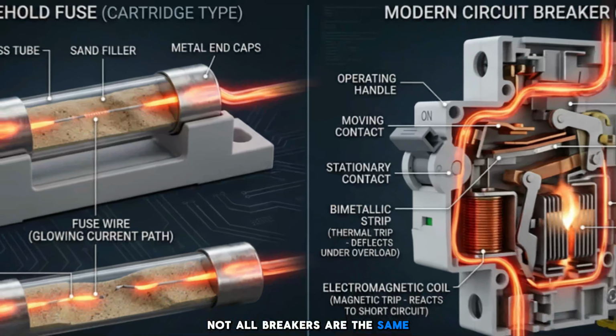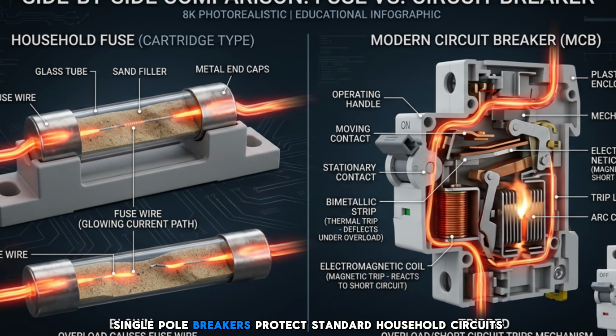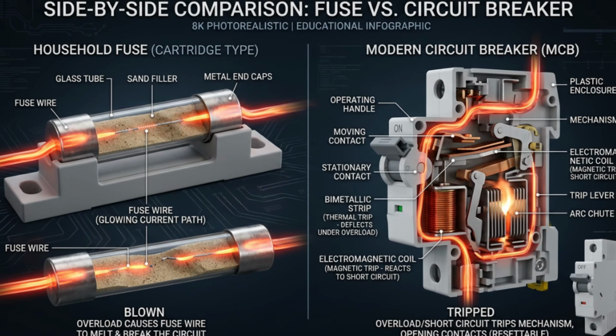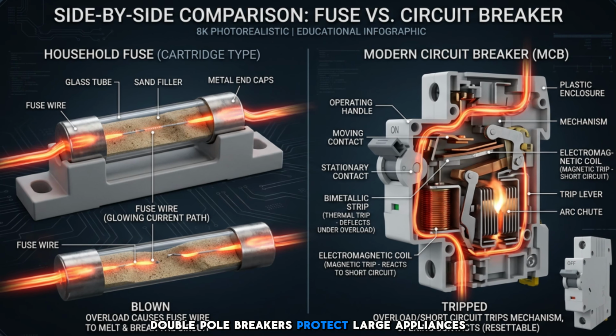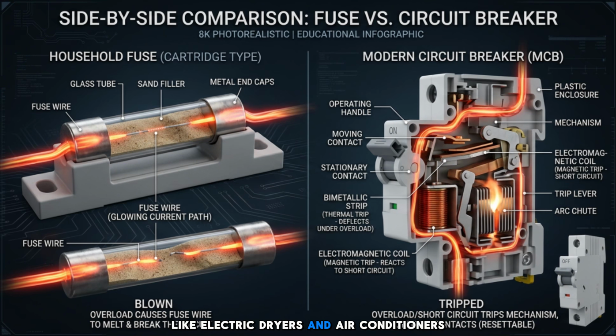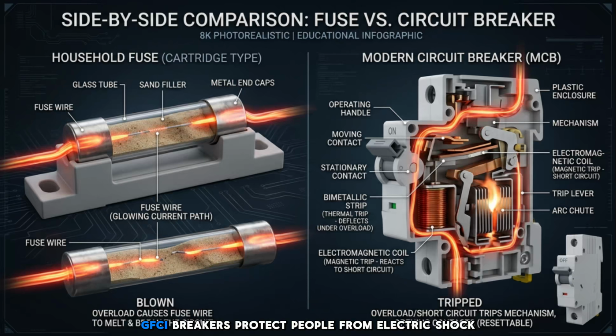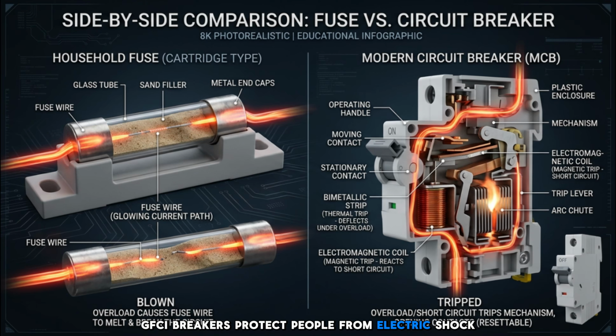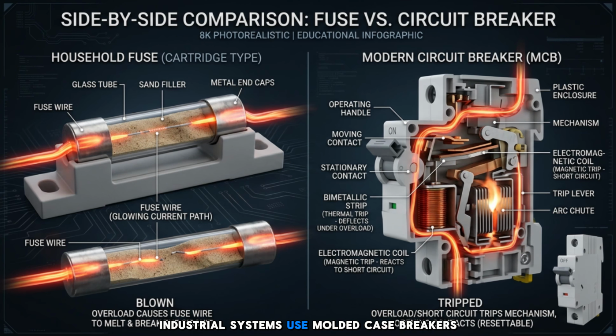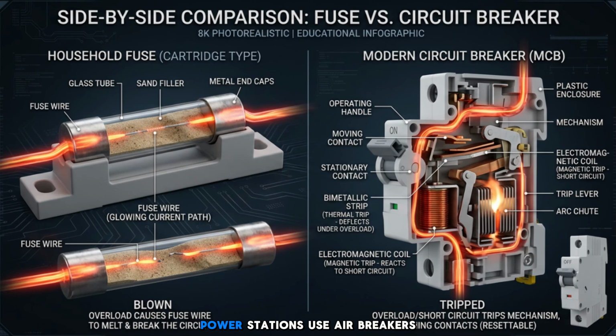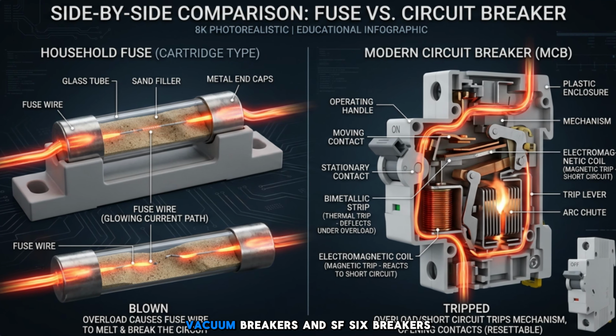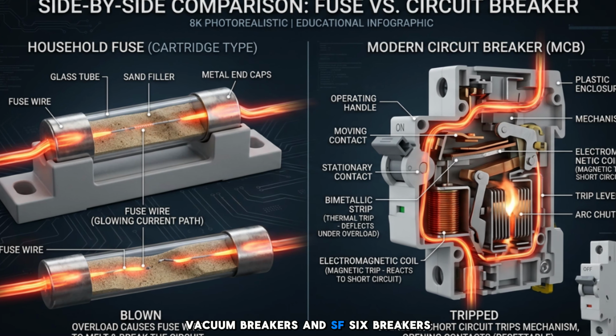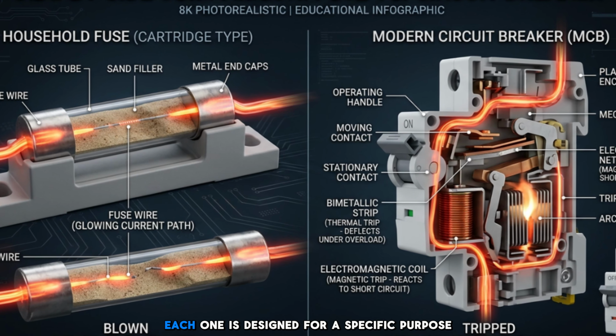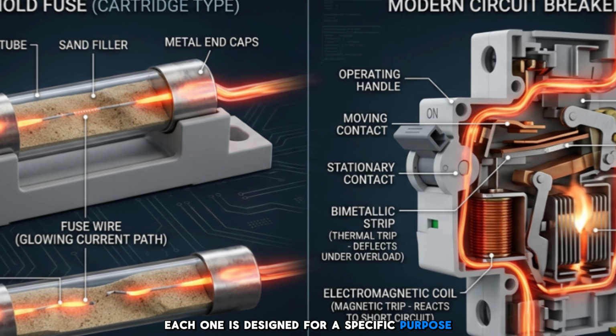Not all breakers are the same. Single-pole breakers protect standard household circuits. Double-pole breakers protect large appliances like electric dryers and air conditioners. GFCI breakers protect people from electric shock. AFCI breakers detect dangerous electrical arcs. Industrial systems use molded case breakers. Power stations use air breakers, vacuum breakers, and SF6 breakers. Each one is designed for a specific purpose.